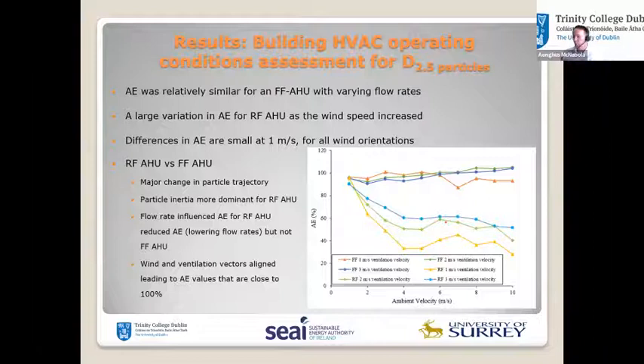But when the air handling unit was facing the opposite direction, so the particles have to go all the way around it and turn into the inlet, you could see the average aspiration efficiency for the average wind speed in Dublin, about 3.5 meters per second, was about 50%. So about 50% of the concentration didn't enter the air handling unit just because it was opposite to the ambient wind direction, which makes a significant difference to the amount of particles going into the building, loading the filter, and the energy consumption over the filter's life. We were very encouraged by that finding.